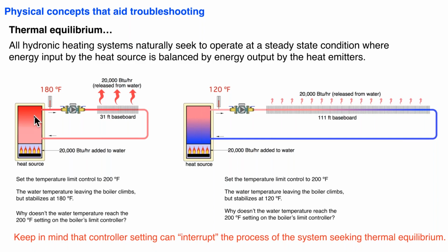That's not a bad thing. In fact, imagine if we had decreased this baseboard to, let's say, 10 feet, and if we didn't have an upper limit control on there, and assuming we've got a pressurized system, the temperature in that system could rise maybe 250, 260, maybe even higher. Those are dangerously high temperatures. So the fact that a control would intervene and shut the system off, shut the heat source off prior to the system reaching thermal equilibrium is a good thing.